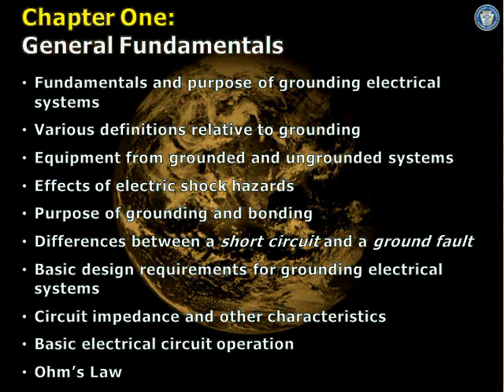Okay, so electrical fundamentals, let's talk about a few things, guys, about just the fundamentals, about grounding and definitions and so forth. Grounded conductor, equipment grounded conductor for grounded and ungrounded systems is a big deal. The shock hazard, everything goes back to 70E and OSHA, right? Why do we care about grounding? If you don't care about killing electricians, like we used to do in the past, you really don't have to worry about pulling an equipment grounded conductor or bonding. If you don't care about burning your building, if you lose a neutral, the main bonding jumper doesn't mean anything to you, right? So it's a whole thing.